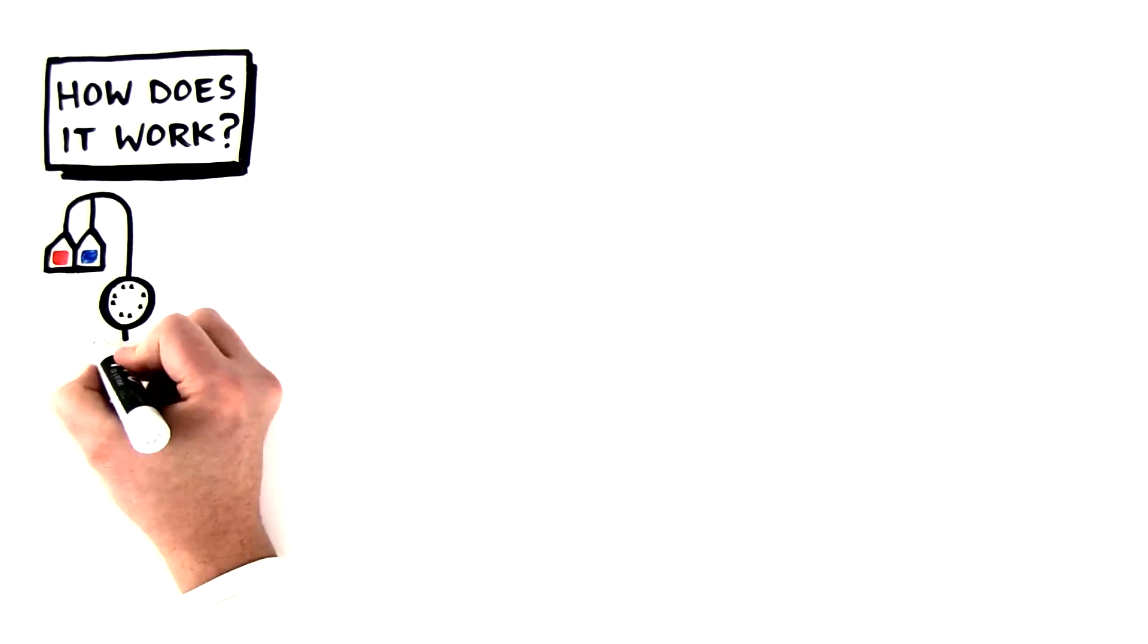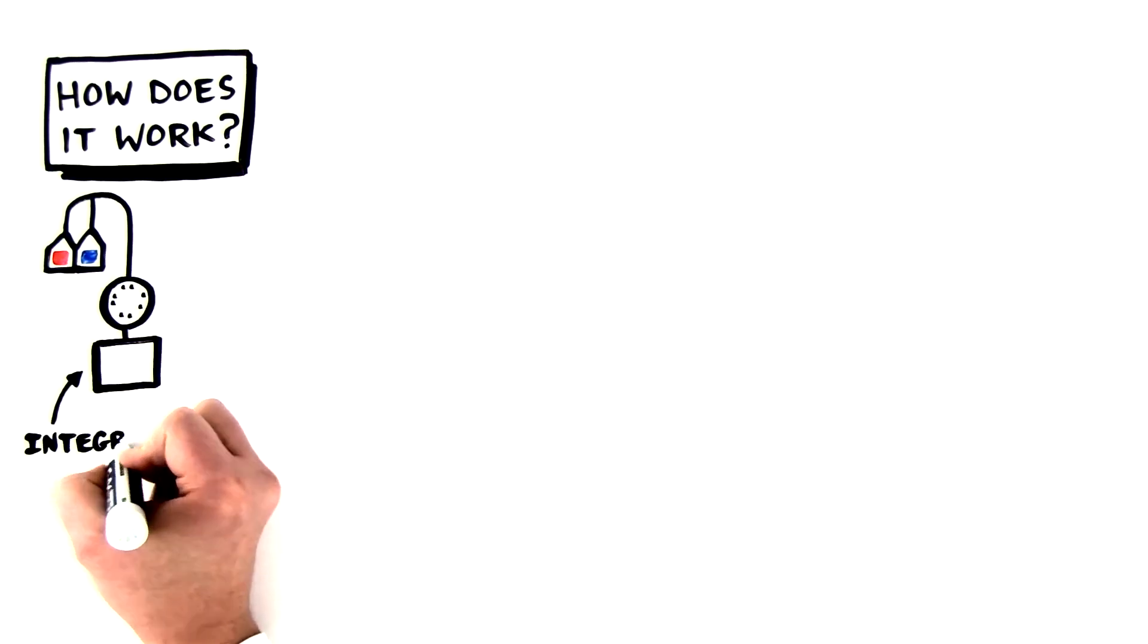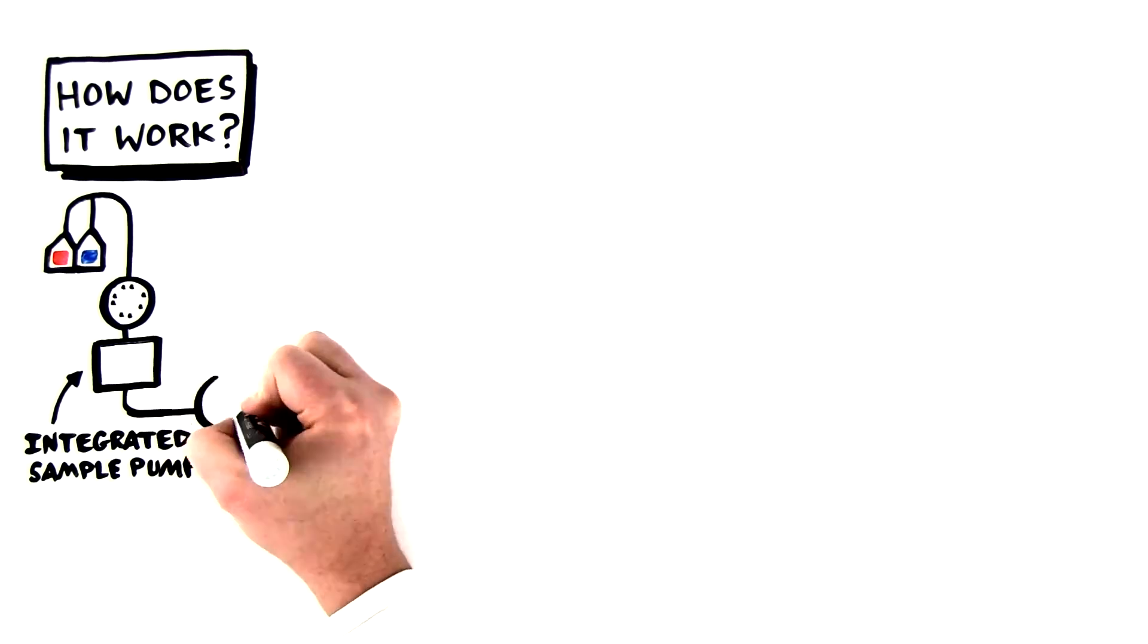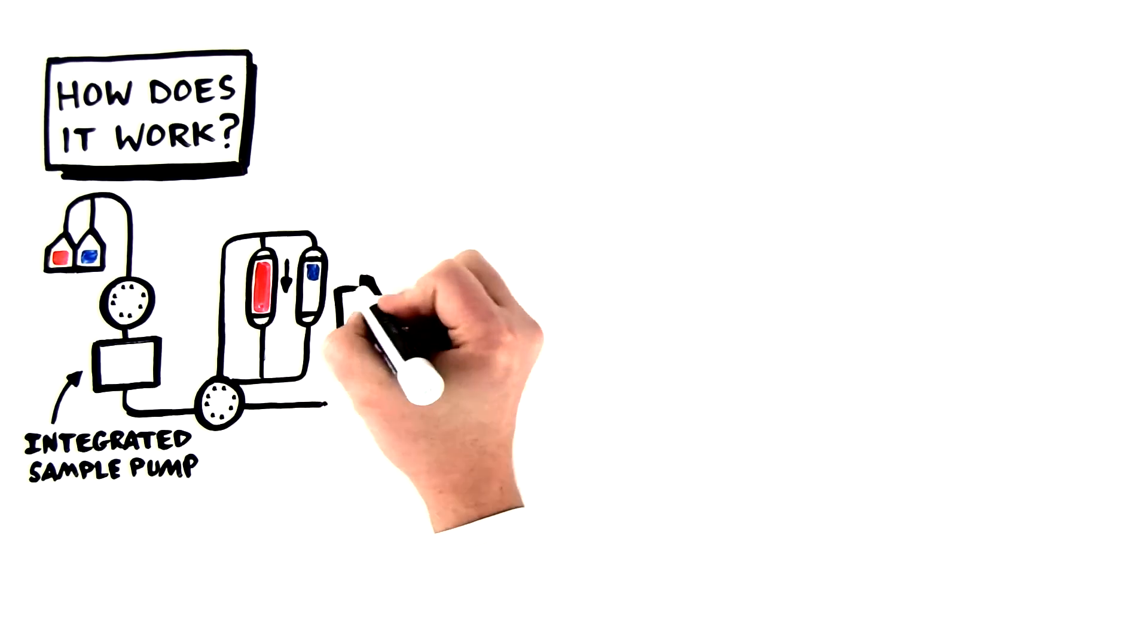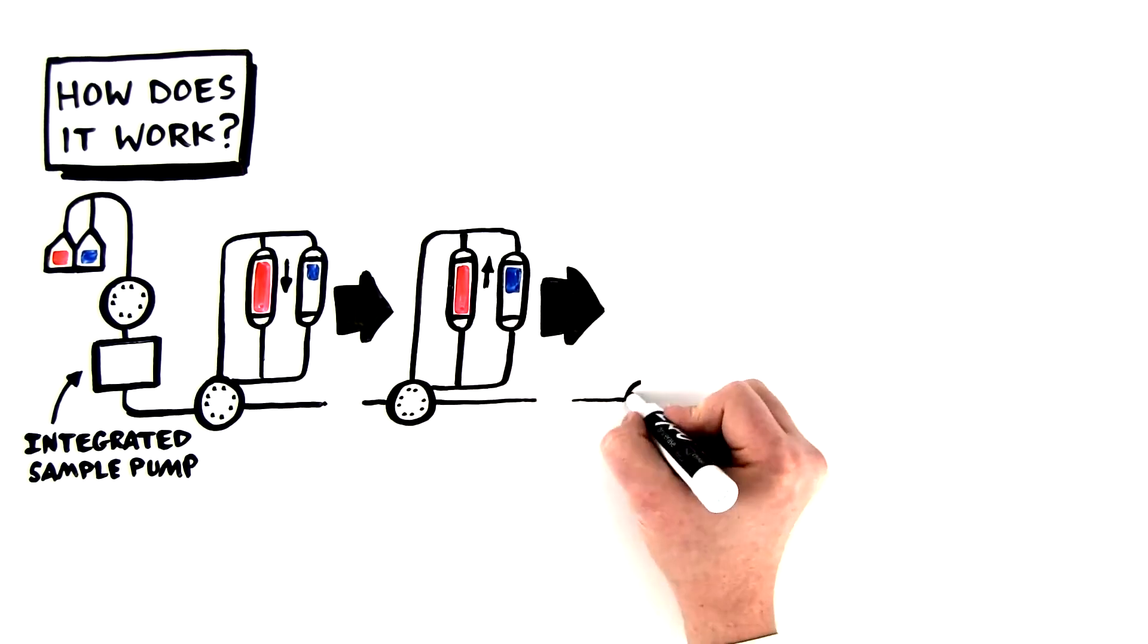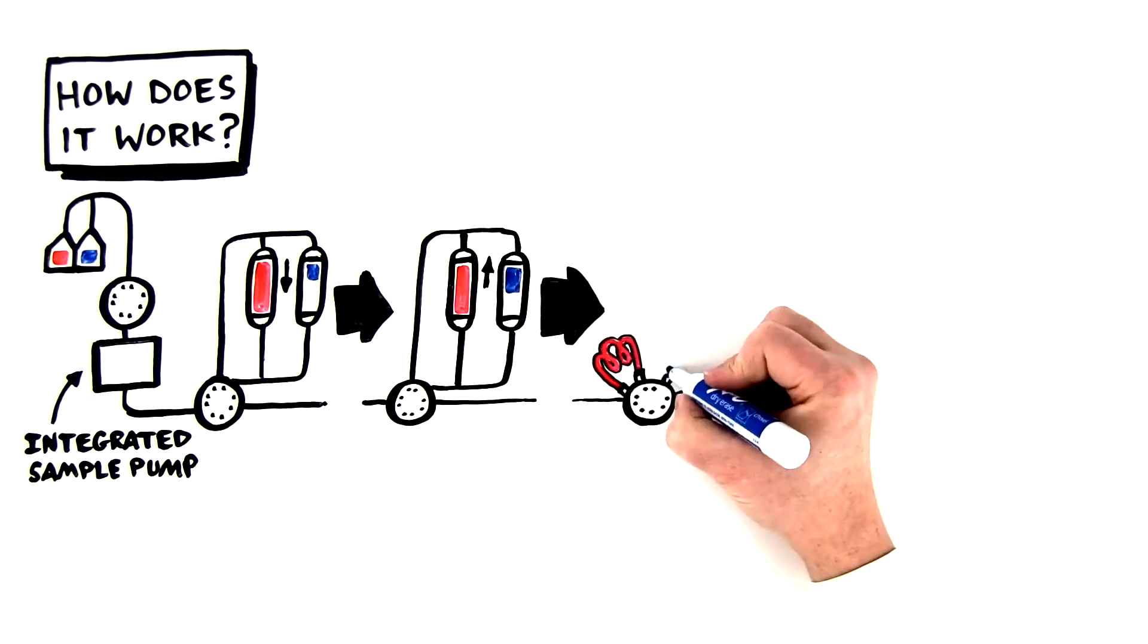But how does it work? Well, in a typical Multi-D workflow, samples are first loaded onto a column using an integrated sample pump. After flow-through and unbound material are washed away, the eluate is shuttled through the detector. Then, samples are taken from key points containing the protein of interest and sent to a loop for storage.